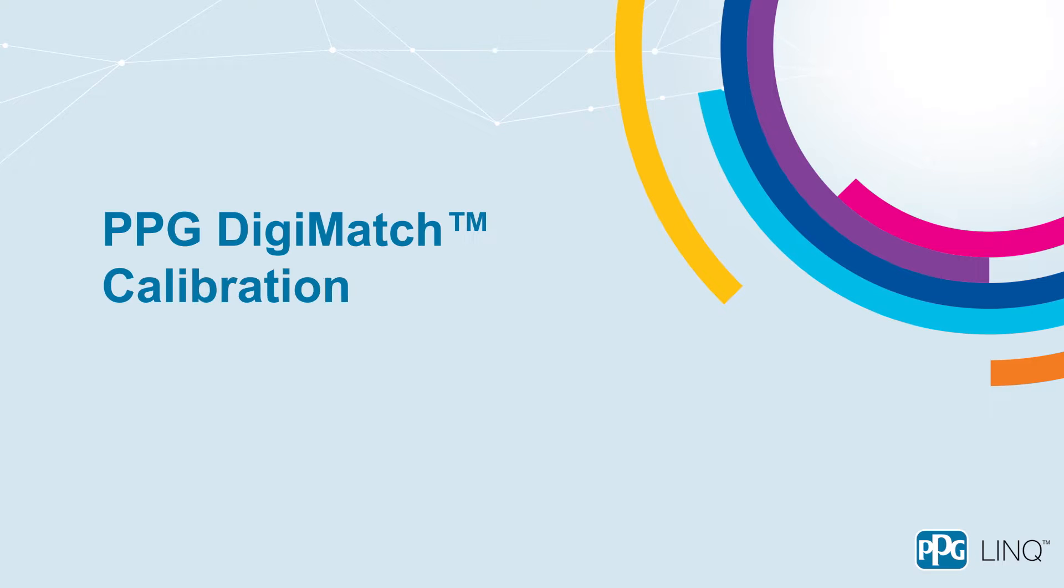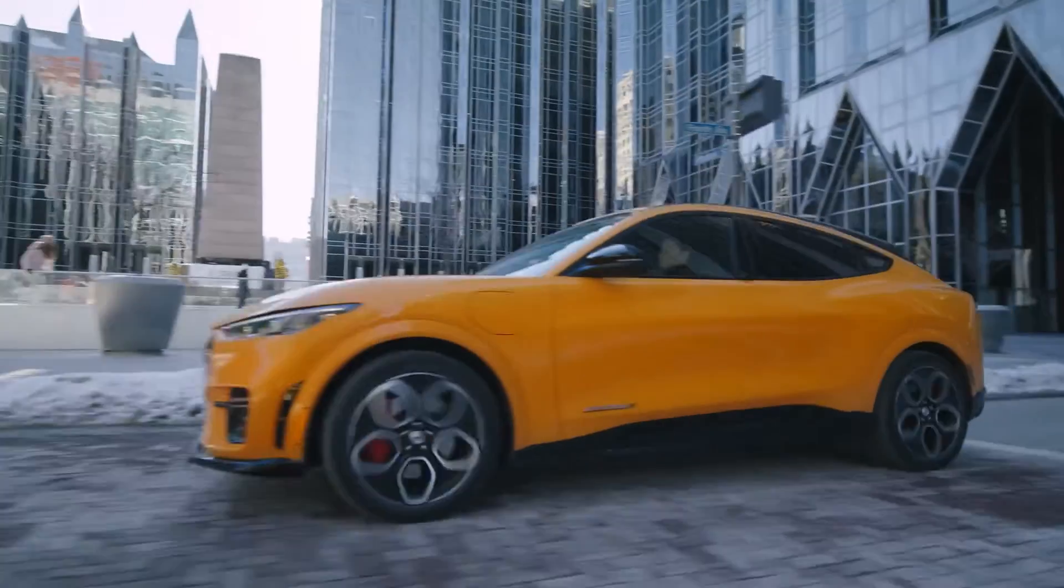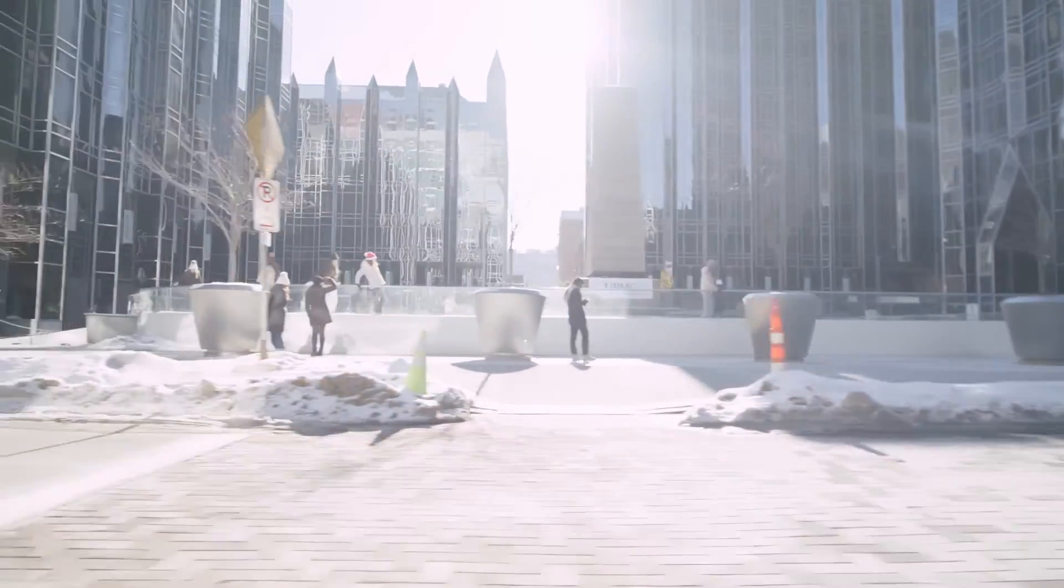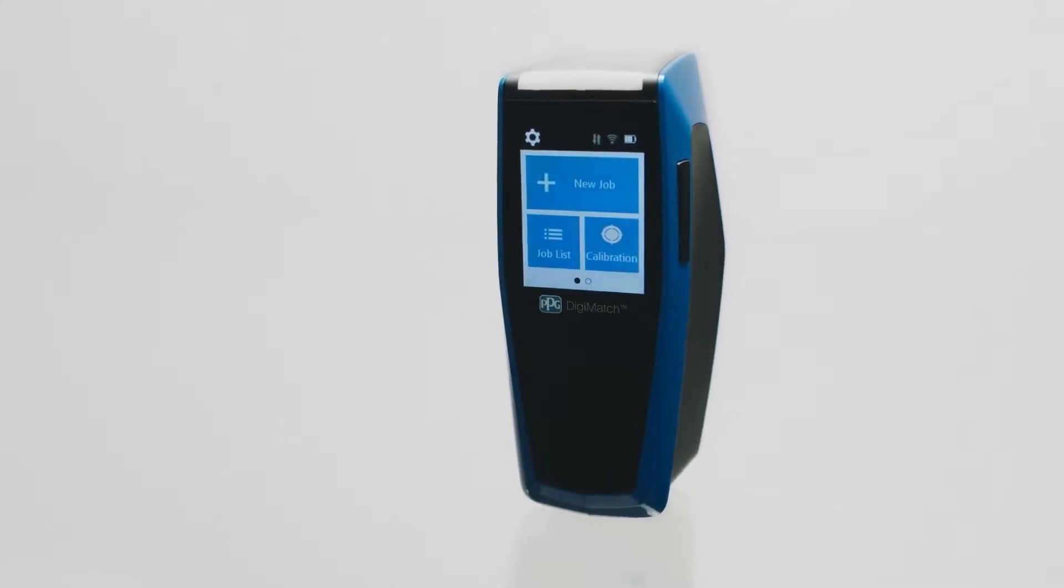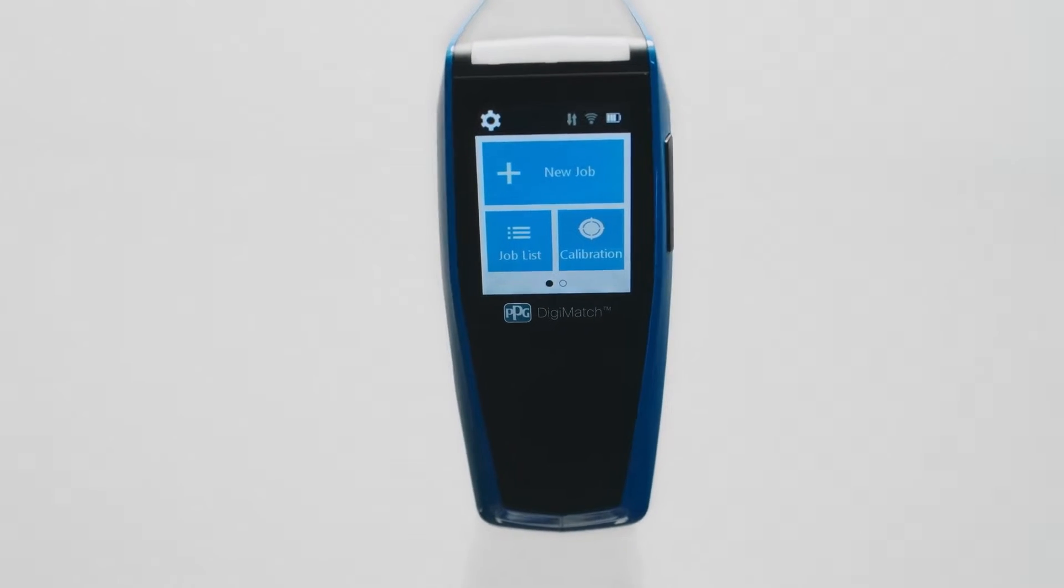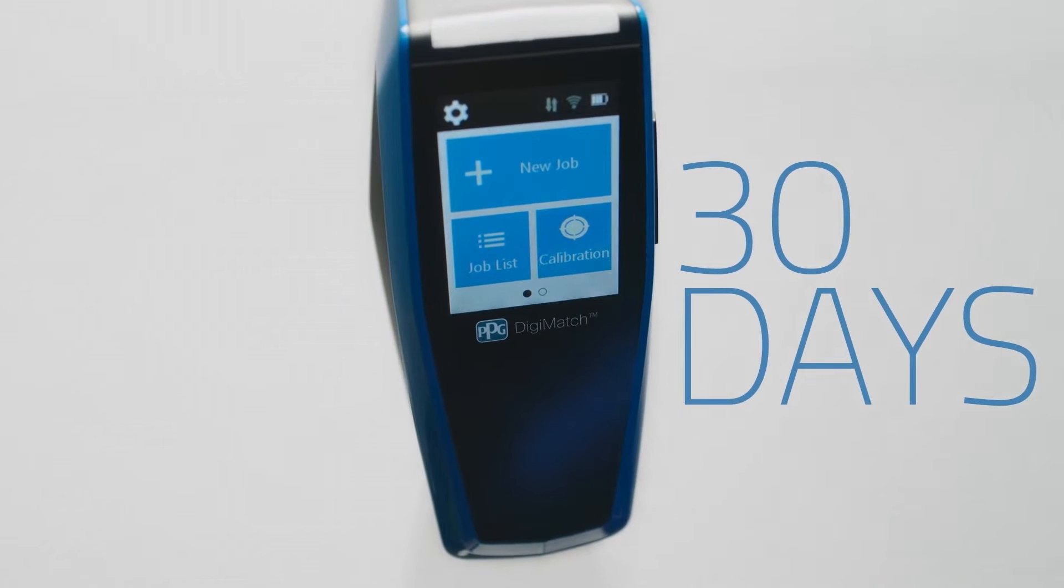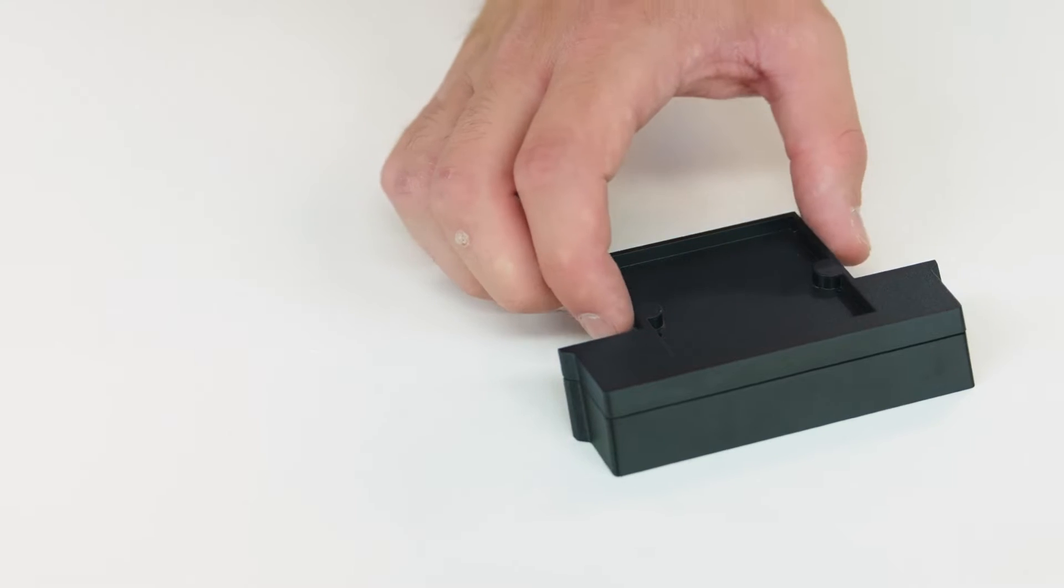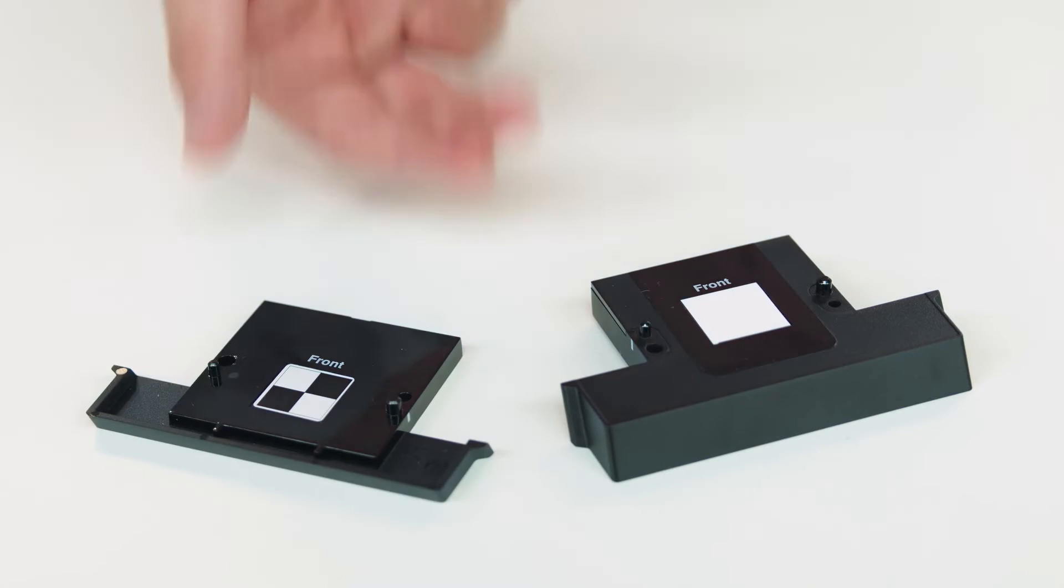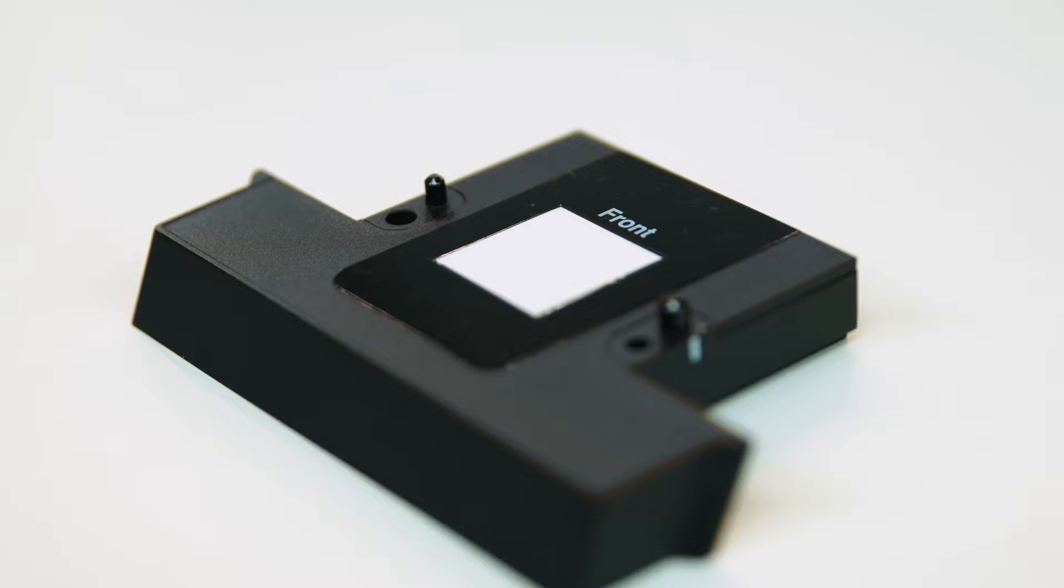PPG Digimatch calibration steps. Before you're ready to take your first color reading, you'll need to calibrate your new PPG Digimatch. It typically takes less than two minutes to calibrate. The spectro needs to be calibrated every 30 days using the calibration tiles supplied. You should not substitute other tiles as the serial number on the reference needs to match the number displayed on the device.